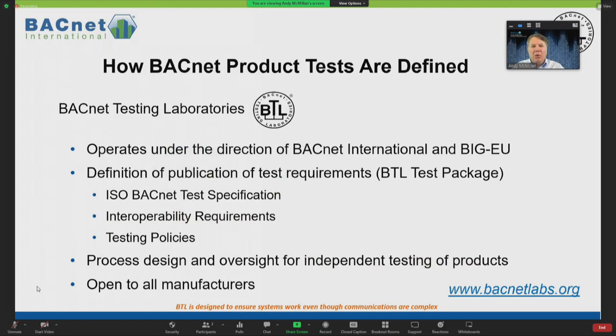The BTL working group is the active working group inside BTL, and it operates under the direction of both BACnet International and BIG-EU. It basically defines and publishes everything you need to know to test BACnet products officially, and they call that collection of documents a BTL test package. It draws from the ISO test specification, interoperability requirements, and includes testing policies.